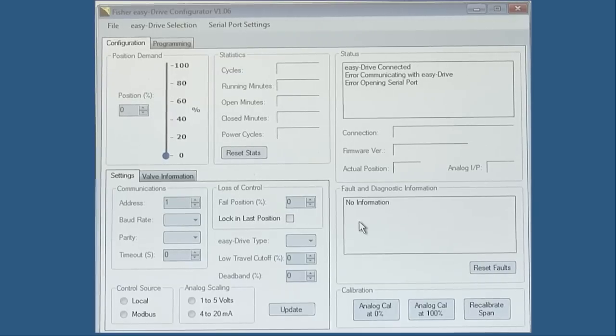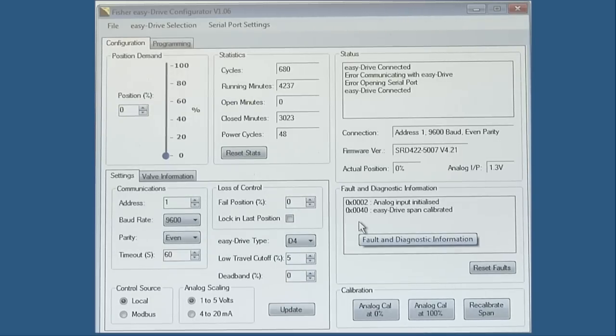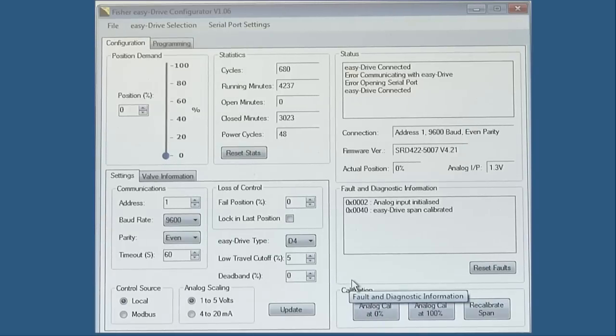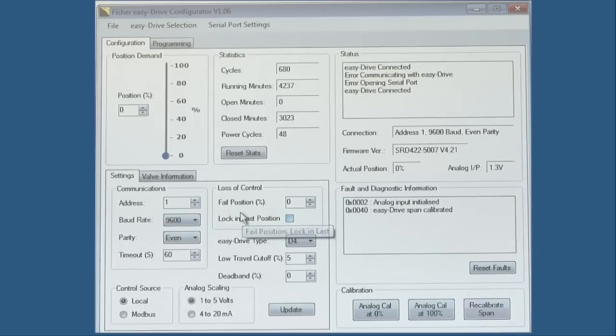Now that you are connected to the easy-Drive, you should see the application has been populated. Again, this configuration software is a graphical user interface that intuitively publishes the Modbus registers. You can change variables such as fail position, low travel cutoff, and the percent dead band you would like to give the actuator.